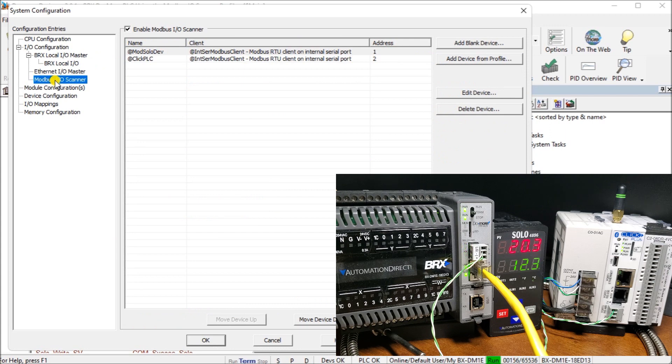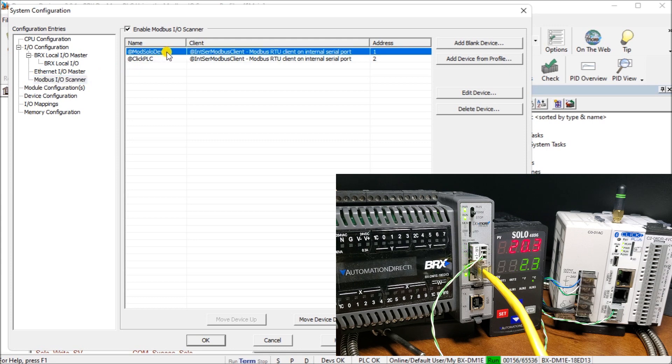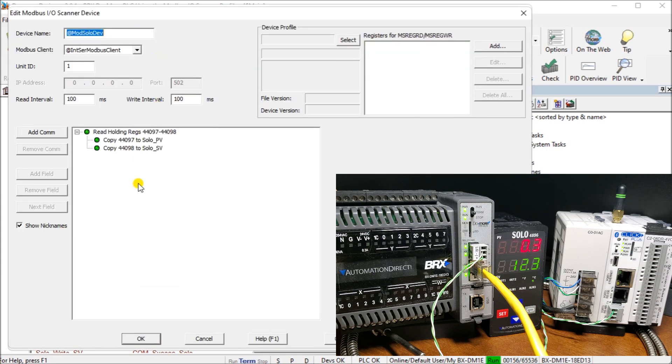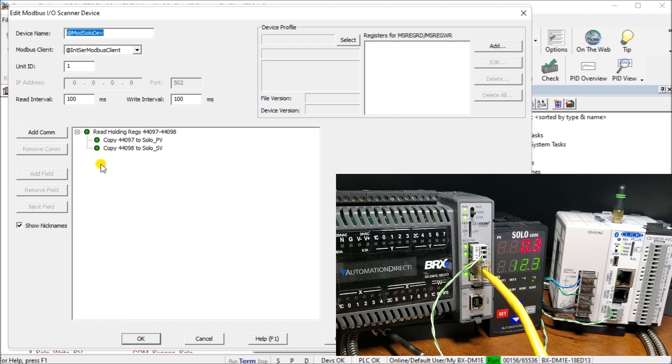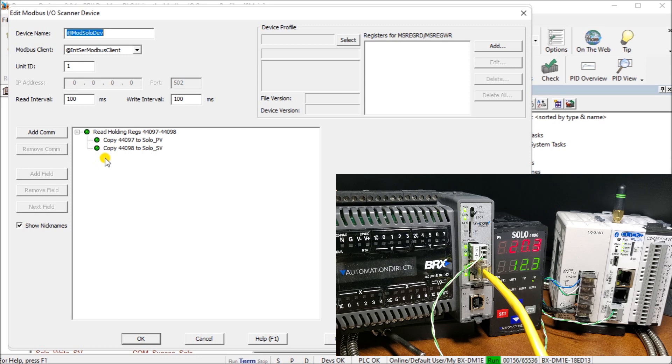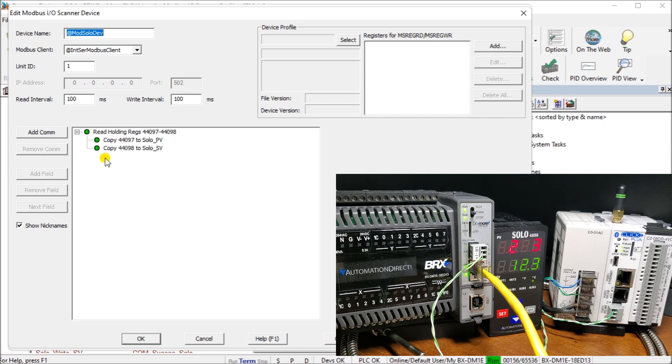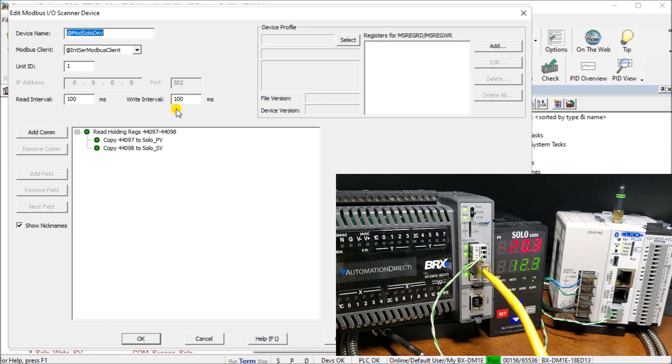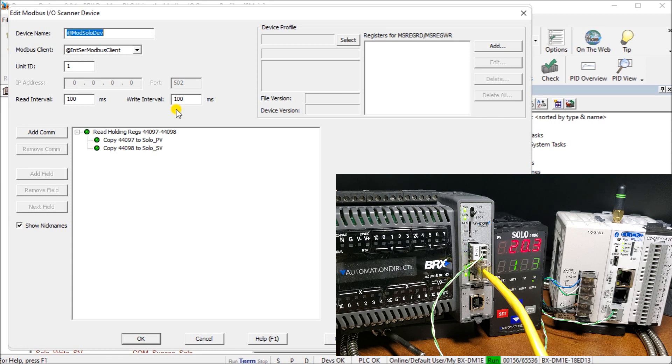Okay then we go to our modbus I.O. scanner. Now when we're in our scanner you can see that we already have our previous modbus solo that we created last time and we'll just double click into that. We've modified it slightly because we only allowed reads in here. So last time we had a write so we eliminated that write simply because if we kept that in, the scanners automatically sequence through and automatically will update. So last time we had a write from v2 so every time anything went into v2 it always wrote every 100 milliseconds. So that means that no other device on the network could actually communicate to that device. So if I were to try to put something onto the solo itself and increase the set value it would overwrite by this instruction here every 100 milliseconds. So we eliminated that and only had reads now into our solo.